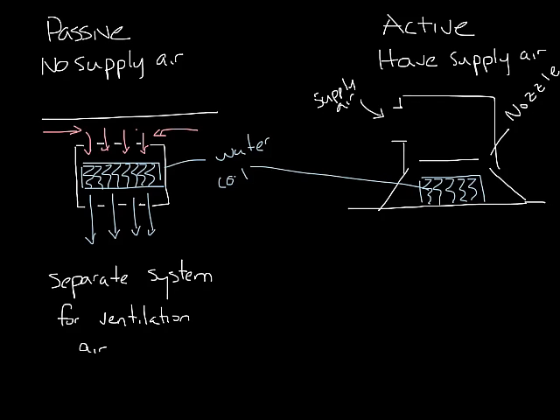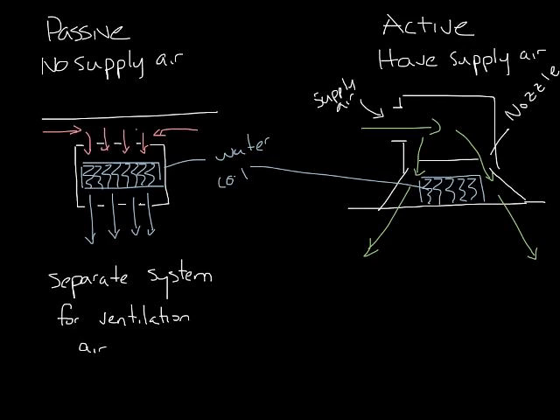So let's look at how this works. Your ventilation air will come in through the inlet and will go through the nozzles and then out slots in the face of the diffuser. This will cause a low pressure zone right in the center of the face of the diffuser, just under the water coil. Warm room air is pulled up over the coil and is cooled down. It is mixed with the ventilation air coming through the nozzles and goes into the space to provide cooling.